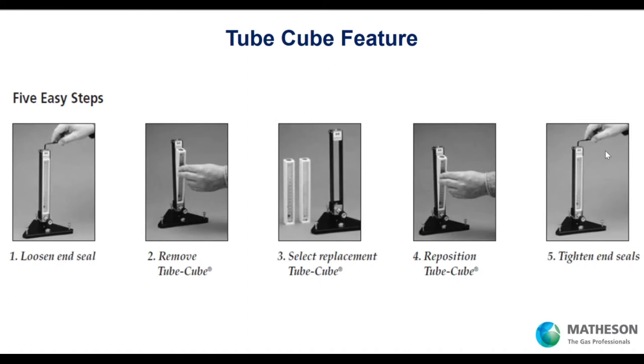The tube cube feature is very powerful. You have your rotameter, you're doing some work, and you'd like to change what you're doing. Take an Allen wrench, loosen the seal, pop out the current tube cube, put in the new one, tighten it up, and you're off and running with a new tube cube. It's a convenient way to change your application without having to buy a whole new rotameter assembly.